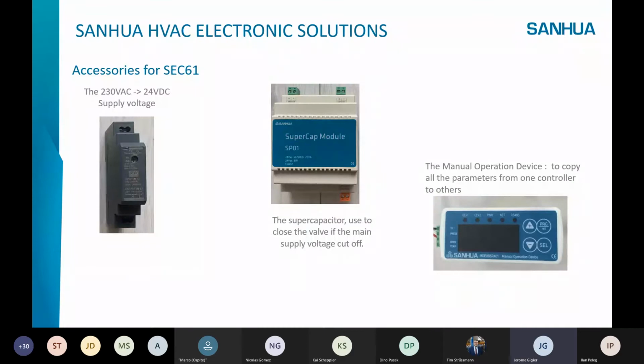We have also some accessories for this SEC61. For this controller, we have the supply voltage to convert 230 volts to 24 volt DC. We have also a supercapacitor, to close the valve when the main supply is cut off. So accidentally, it's possible that the voltage switches off, so the supercapacitor is able to close the valve. And we have also a manual operation device, to copy all the parameters from one controller to another controller.